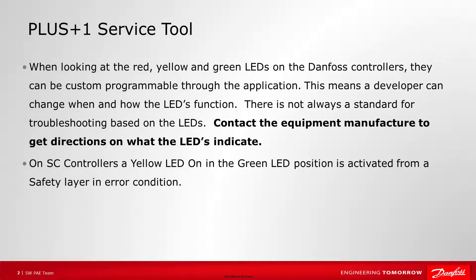Oftentimes, the LEDs on hardware can be helpful when troubleshooting. In the case of Danfoss controllers, the red, yellow, and green LEDs can be custom programmed through the application, meaning a developer can change when and how the LEDs function. So there's not always a standard for troubleshooting based on the LEDs. Contact the equipment manufacturer to get direction on what the LEDs indicate. One default condition to mention is on SC controllers, where the default is for the yellow LED in the green LED position to be activated for a safety layer error condition.